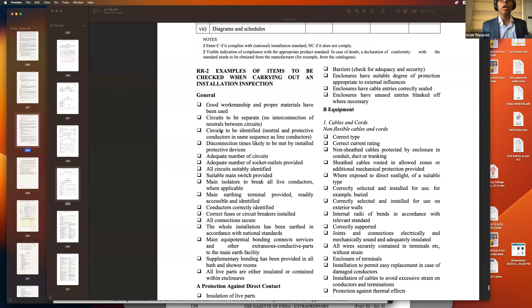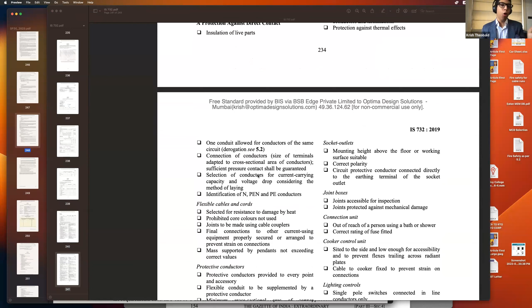So if you look at the checklist here in IS 732 and NEC, they are asking us: is the main earthing terminal provided? Are connections secure? Is one conduit allowed? This is a very specific question, and in fact all of these refer to specific clauses in IS 732 and NEC. So you are essentially checking compliance with IS 732 and NEC, and especially when it comes to the actual tests, these are required on a per circuit basis.